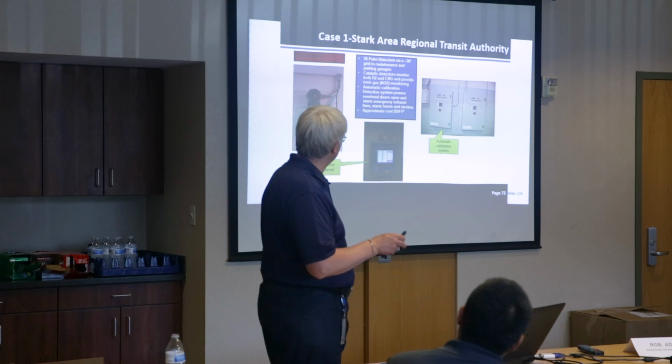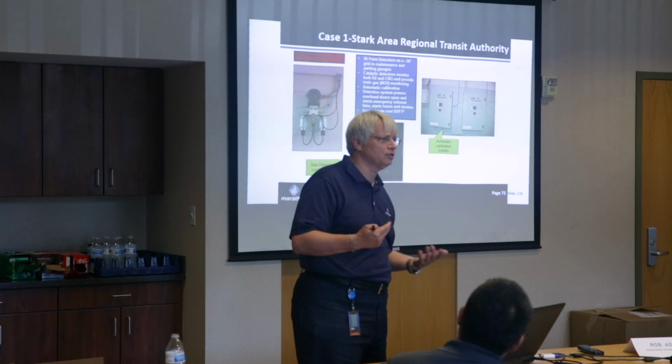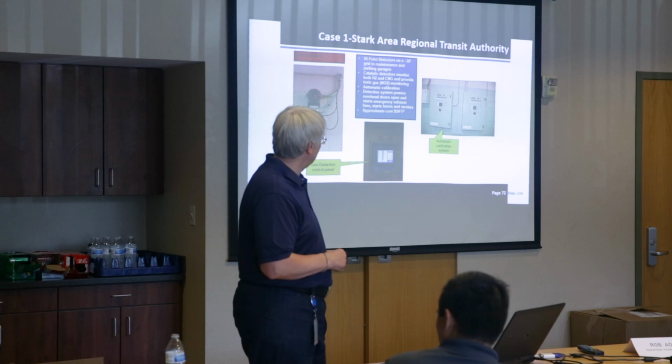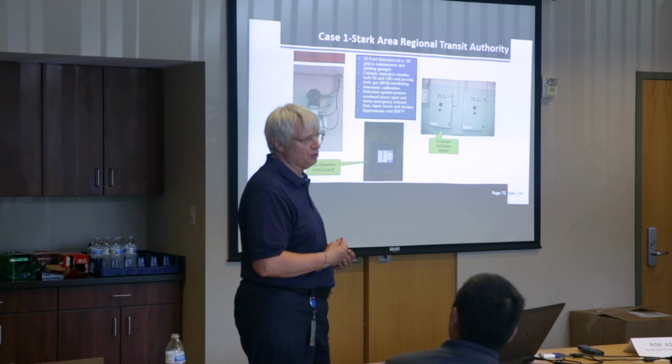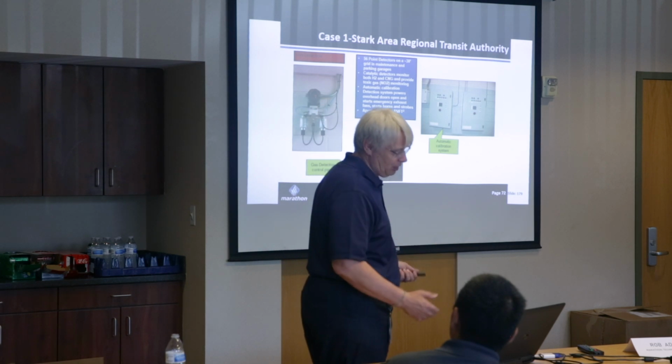Automatic calibration, I don't want to steal the story there, so let's get beyond that. The detection system powers open the overhead doors, starts the emergency exhaust fans, and activates horns and strobes. And the approximate cost was about $5 per square foot. So, a pretty comprehensive system.